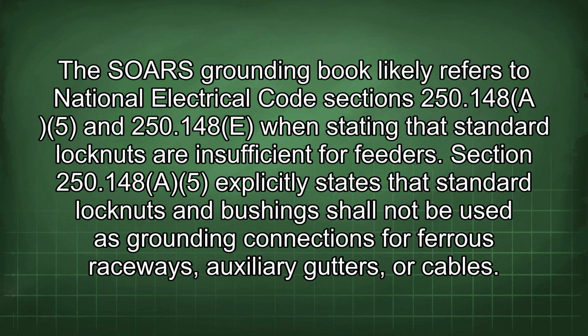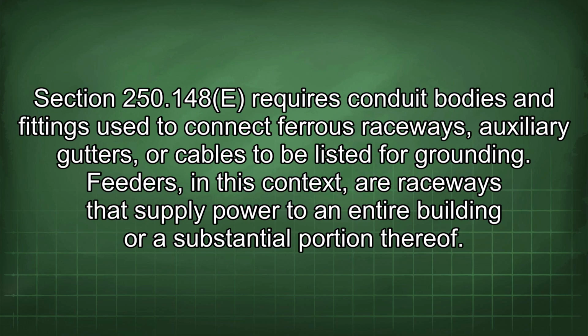The SOARS grounding book likely refers to National Electrical Code sections 250.148 and 250.148E when stating that standard locknuts are insufficient for feeders. Section 250.148 explicitly states that standard locknuts and bushings shall not be used as grounding connections for ferrous raceways, auxiliary gutters, or cables. Section 250.148E requires conduit bodies and fittings used to connect ferrous raceways, auxiliary gutters, or cables to be listed for grounding. Feeders, in this context, are raceways that supply power to an entire building or a substantial portion thereof.